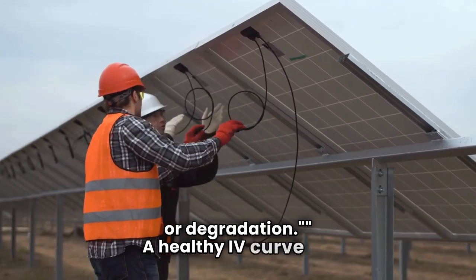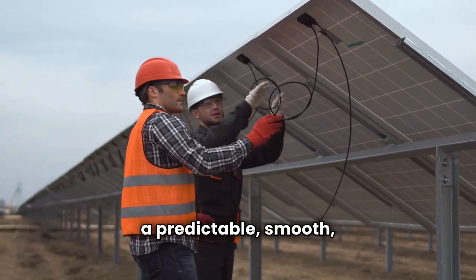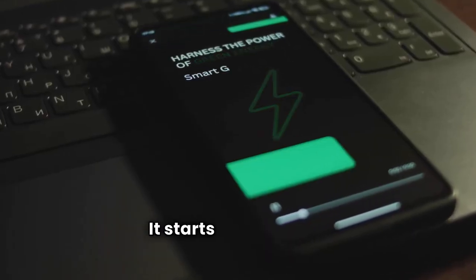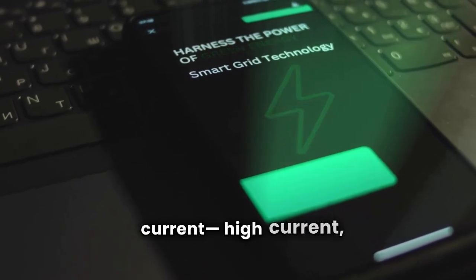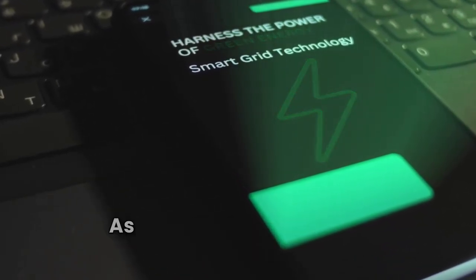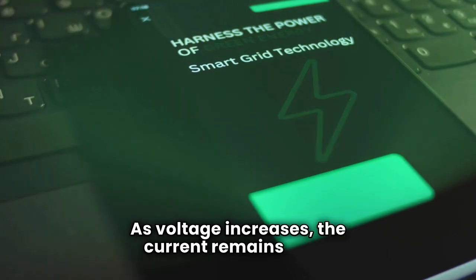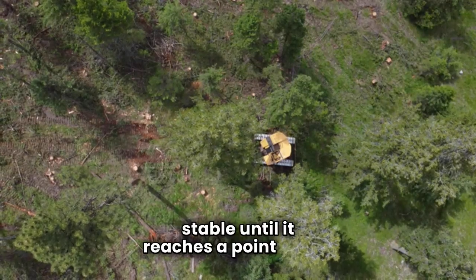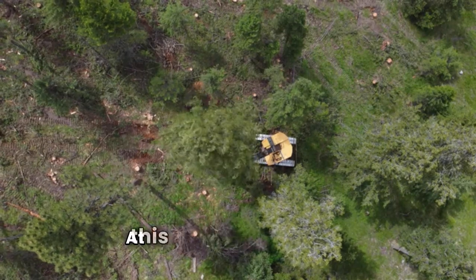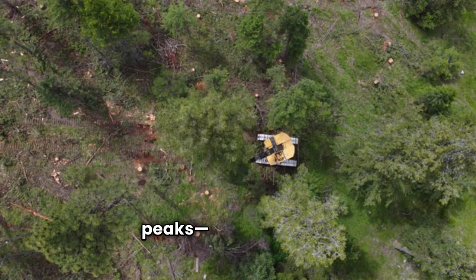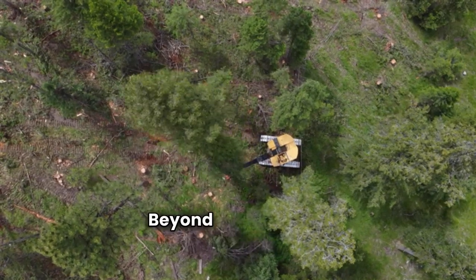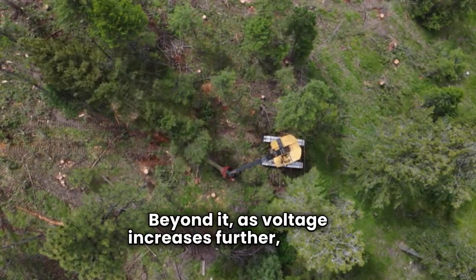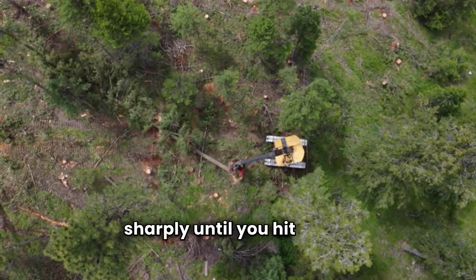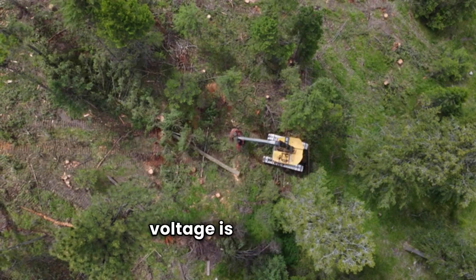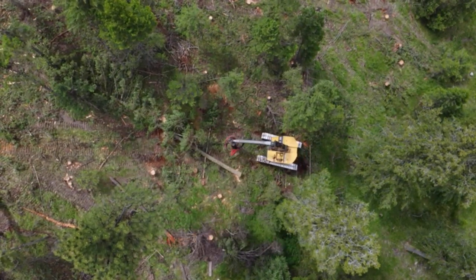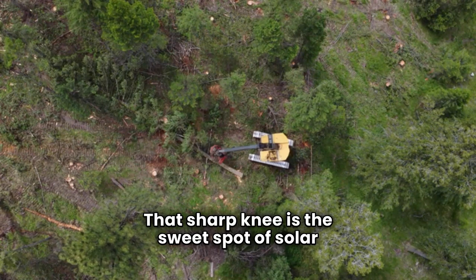A healthy IV curve has a predictable, smooth, almost graceful shape. It starts at the short circuit current, high current, zero voltage. As voltage increases, the current remains fairly stable until it reaches a point called the knee of the curve. At this knee, power output peaks, the maximum power point. Beyond it, as voltage increases further, current drops sharply until you hit open circuit voltage, where voltage is maximum but current is zero.